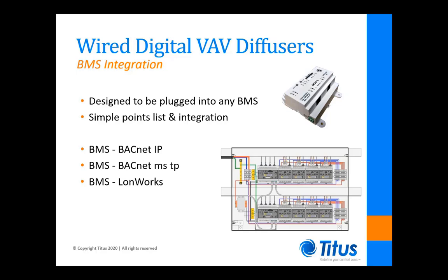The VAV diffuser system can be integrated into any BMS that uses BACnet IP, BACnet MSTP, or LONWORKS communication standards. The master communication module is also available as a standalone option, which is useful for smaller projects that do not have the budget for a full BMS. The standalone option relies on the software that is provided with the VAV diffusers for centralized control of the system.